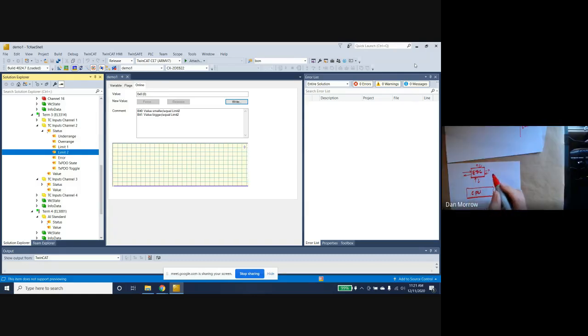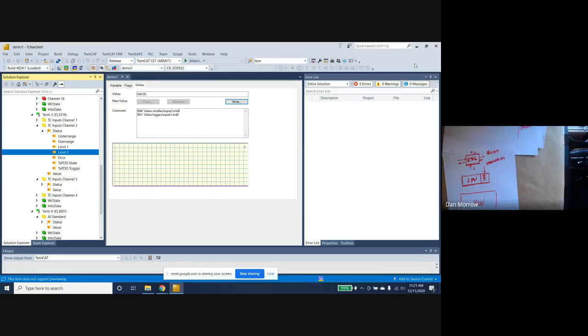But attached to this EtherCAT network interface chip, there is a CPU in every one of these slices. What the CPU does is maintain a bunch of variables that refer to the state of the hardware underneath it. So literally, in the case of the temperature TC inputs, the EL3314, the ESC chip is picking up these packets and rebroadcasting. The CPU is checking the bits it sees in the shift register to see if it's for this unit or not.